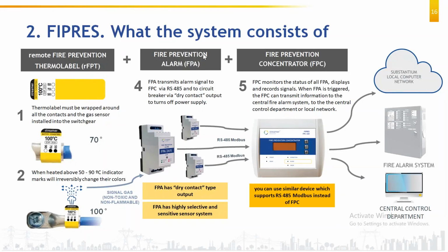This gas will be sensed by the FPA. So this is the function of the FPA. FPA is basically a gas sensor and a communication device. The gas which is coming out of the sticker is going to be sensed by the FPA. FPA transmits an alarm signal to the FPC via RS-485. If gas is there, it will give an alarm, and then it will communicate that change in state to a remote monitoring device, which is the FPC, through RS-485 communication, and it also has a dry contact which can be used for local annunciation.